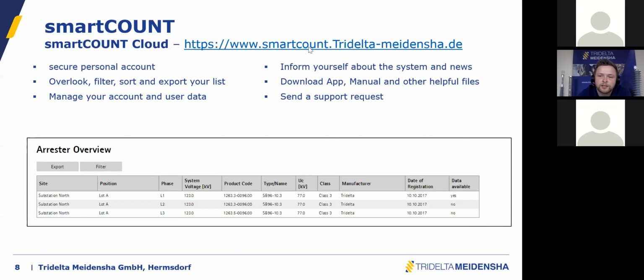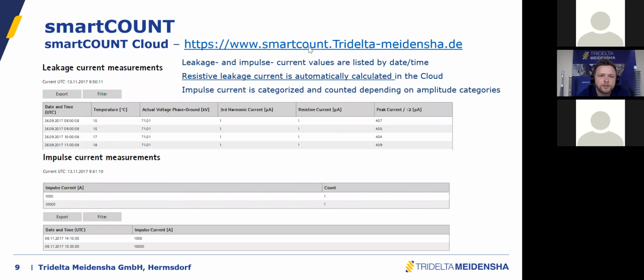And now you might click on the first surge arrester, yes, data available, I want to see it. And then you see an overview of leakage current measurements, which have been taken automatically or by hand. There are several ways. Here we see cyclically recorded leakage currents at 8 o'clock, 9 o'clock, 10 o'clock, 11 o'clock. So these are automatically generated leakage current measurements. Very low resistive current, of course. This is an example of a very special surge arrester configuration with low peak current and low resistive current.